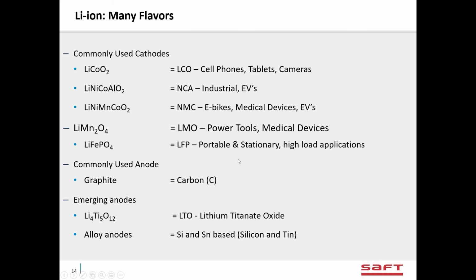When you talk about lithium, there's a lot of different recipes to make lithium-ion batteries. You can use metal oxides, which are cobalt based. You can use nickel, cobalt, and aluminum mixed together, nickel, manganese, and cobalt, manganese oxides, iron phosphates. These are all cathode materials that we talk about. So typically, if you see these letters after your battery, NMC, NCA, LFP, that's telling you what's on the cathode, and they have different characteristics we're going to take a look at.